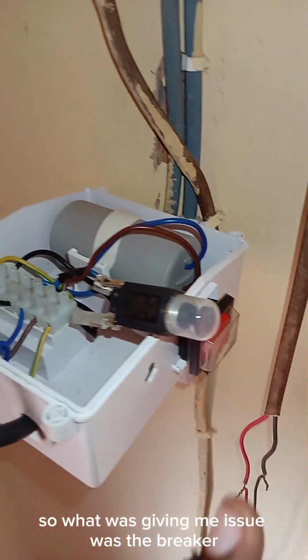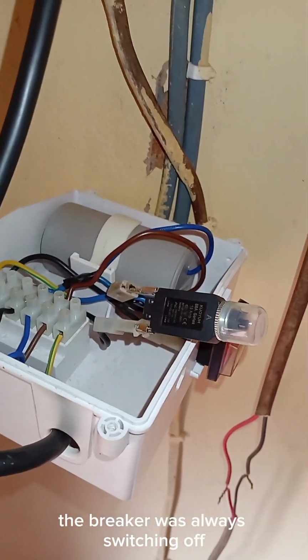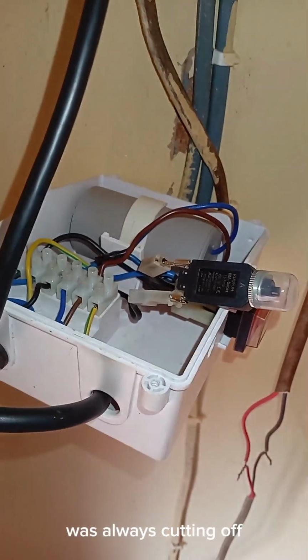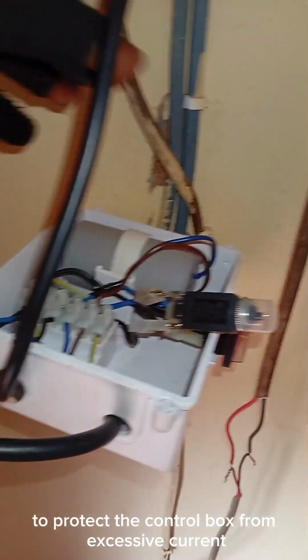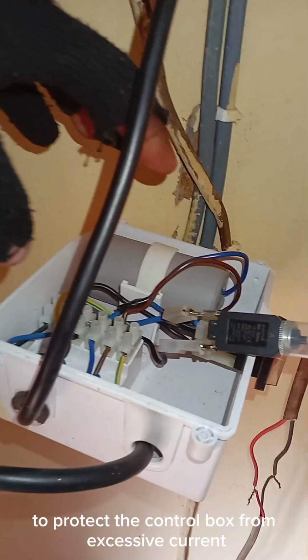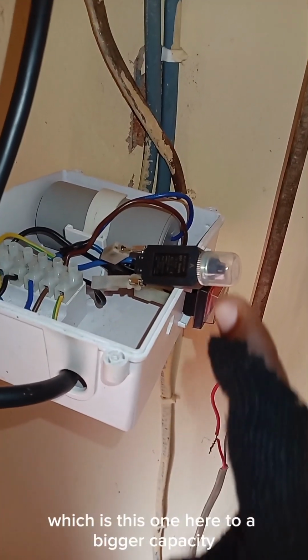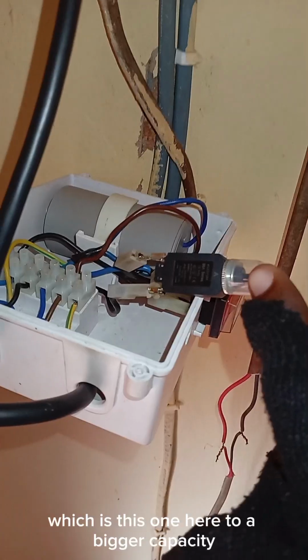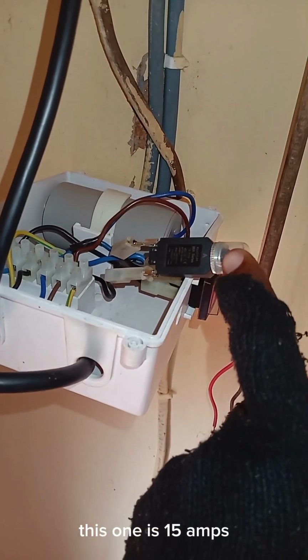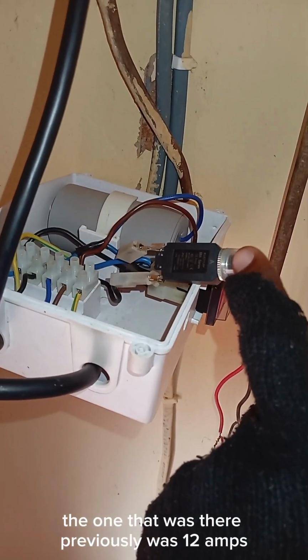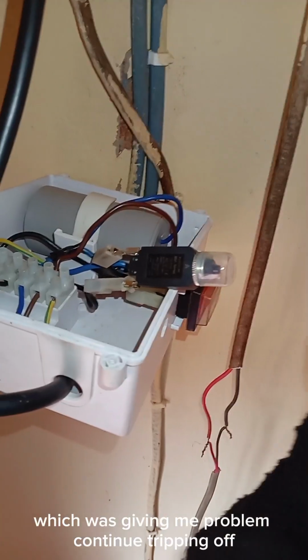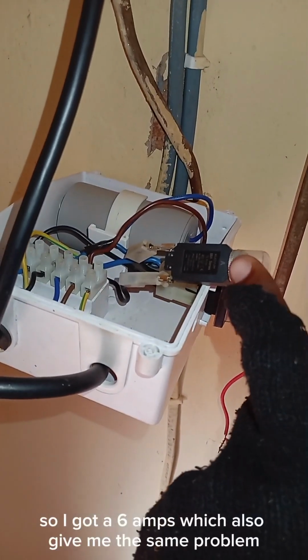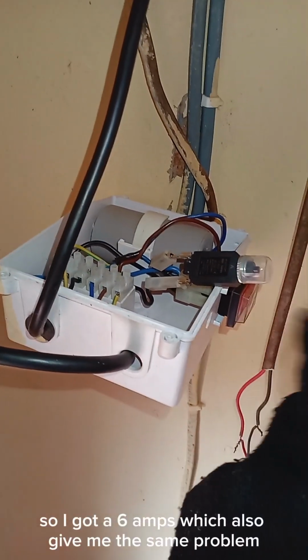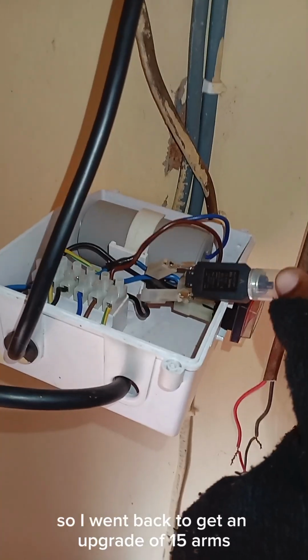What was giving me issue was that the breaker was always switching off, always cutting off to protect the control box from excessive current. So when I changed the circuit breaker, which is this one here, to a bigger capacity, this one is 15 amps. The one that was there previously was 12 amps, which was giving me problem, continuing tripping off. So I got a 6 amps, which also gave me the same problem. So I went back to get an upgrade of 15 amps.